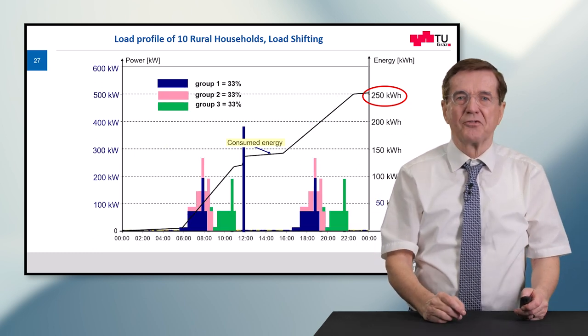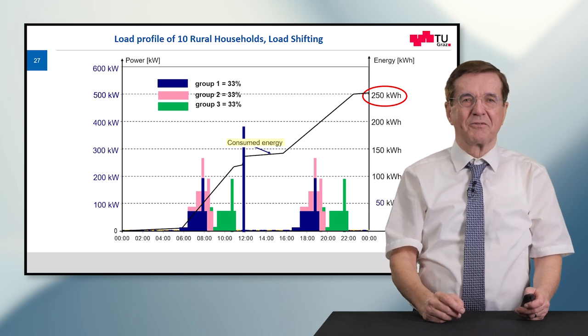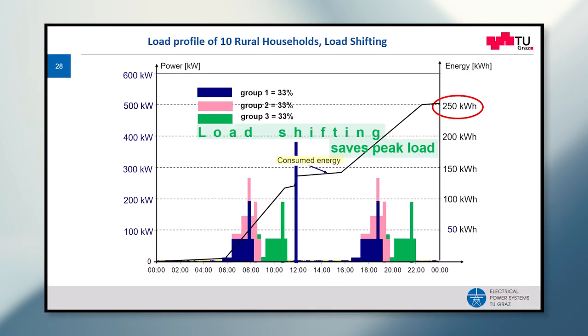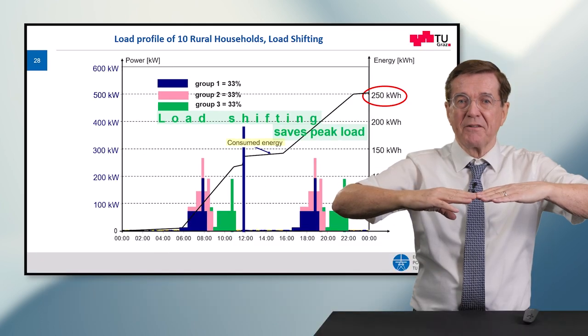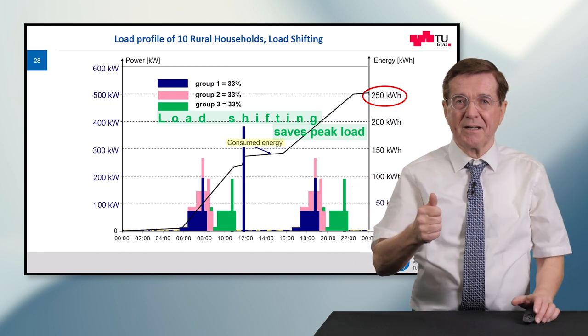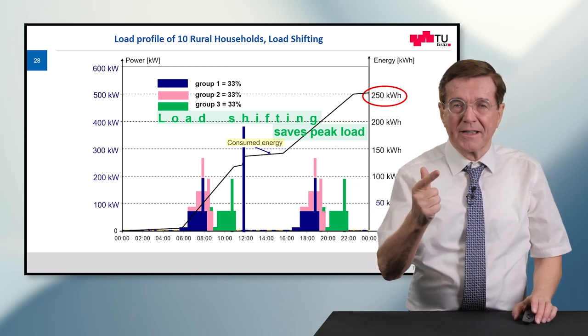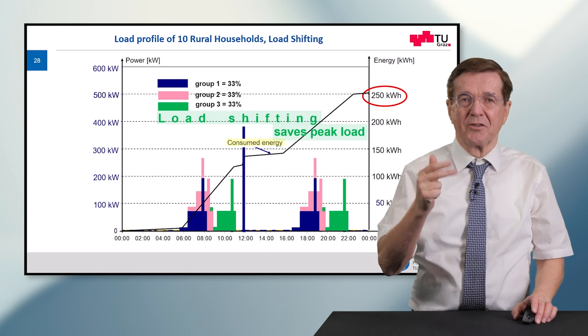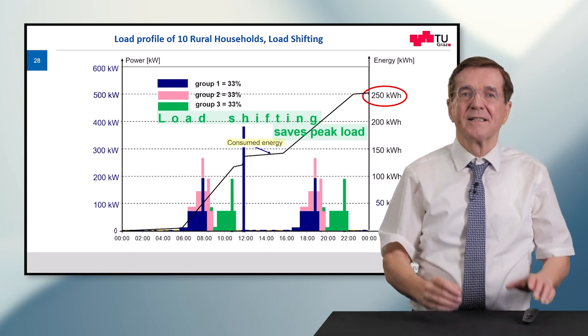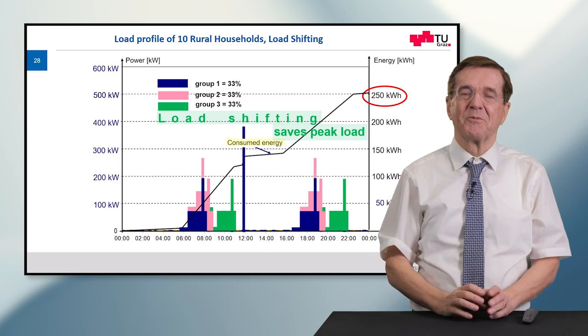This can be extended even to three groups, and you can see what we achieve: the three groups through load shifting save the peak load. We can get more energy through the same type of cable with less peak load. This is the benefit of load shifting — saving peak load and getting more energy through an already installed line — but it requires some adjustment of consumer behavior.